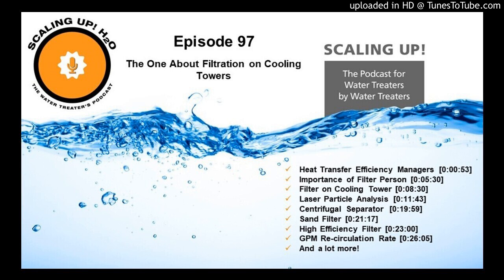Well, it's only going to be there for a day or so. The filter design that I always recommend as far as backwash goes is it needs to be set on a timer to backwash once a day if it hasn't backwashed in the last 24 hours. So it needs to backwash every 24 hours. And the reason for that is that in the media, the particulate that's in there is full of bacteria. And if you leave that bacteria in there for 3 or 4 or 5 days, you're going to plug up the filter bed, and the filter bed has to be replaced.